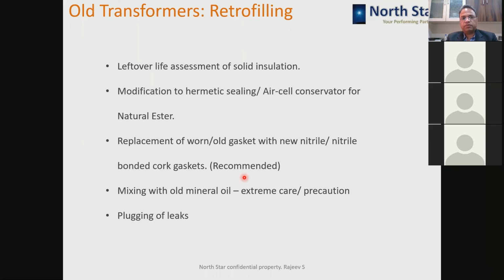Okay. Old transformers: what you can do with old transformers is retrofilling. You can do a leftover life assessment by conducting some tests. We can help you in doing that of solid insulation, and based on that, the transformer can be modified for natural ester to make it hermetically sealed, or by putting the air cell in the conservator. The old gaskets, it's advisable to replace with nitrile or nitrile bonded cork gaskets, and mixing with old mineral oil is to be avoided, because that will degrade the properties of the synthetic and natural ester for which we are going.